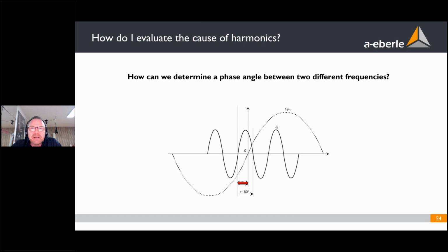How we can detect the phase angle of two different frequencies is not so easy to understand. If you have a vector diagram, the fifth harmonic is 5 times faster than the fundamental. So how can we calculate a phase angle here? Our analyzers detect the phase angle between two different frequencies at the zero crossing of the fundamental. The fundamental of the voltage is a basis. And then we calculate the phase angle to this basis of all voltage harmonics and current harmonics.